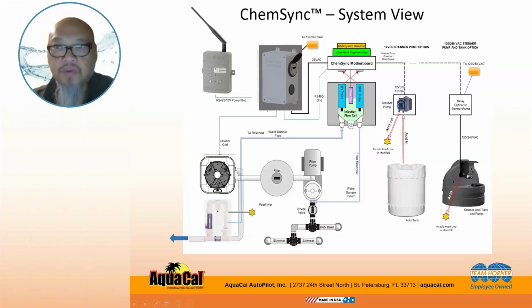So we're doing a couple things by feeding the acid into the manifold. The first thing is, we've got a tendency for scale to build up in the cell because of the rising pH. By adding the acid at this point, it's going to give us a couple of benefits. The first is that it helps keep that cell clean of any kind of calcium scale buildup.